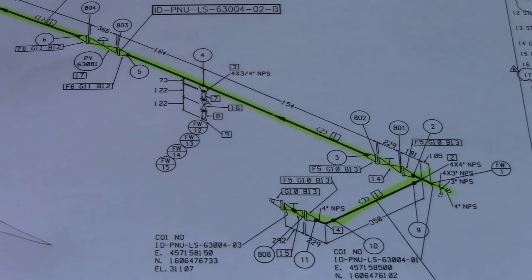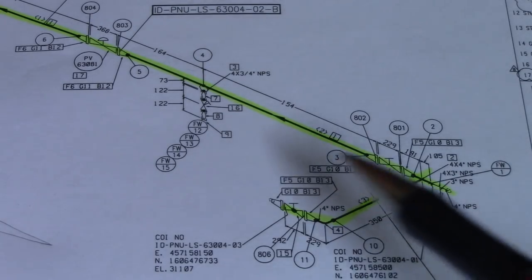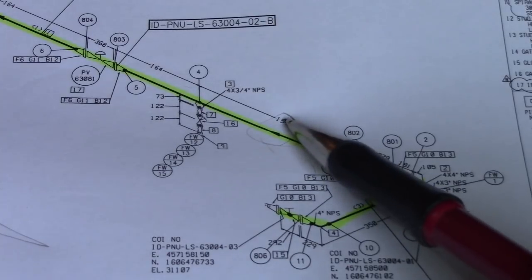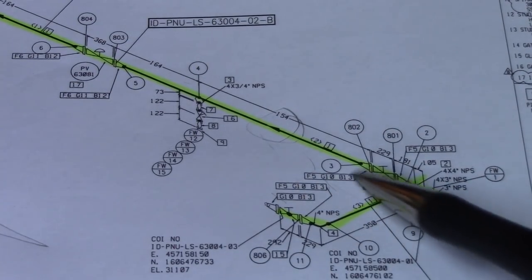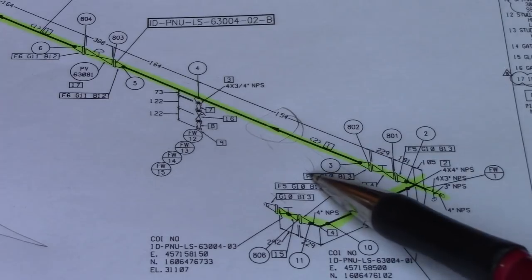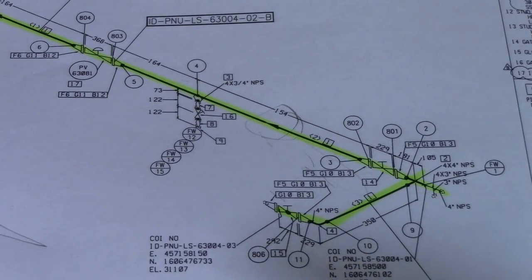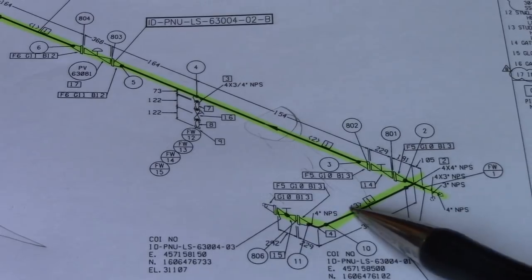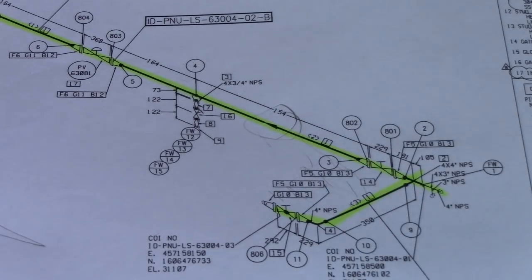Number sixteen is flow direction. We will see here a small triangle on the line of this isometric drawing — that indicates the flow direction. Based on the orientation, the flow is going north. Always check the flow direction, especially when installing check valves, because check valves are one-direction only.